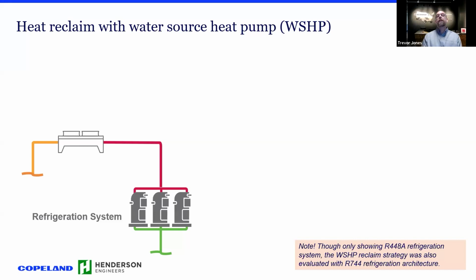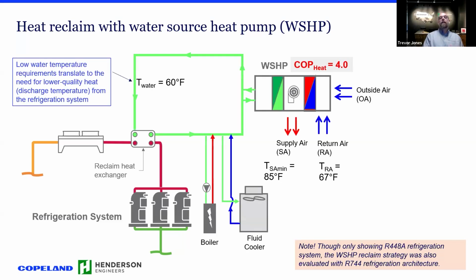So when we start getting into heat reclaim with the water source heat pump system, there's a heat exchanger on the compressor outlet, and our loop feeds through that heat exchanger. That allows us to basically shut off the boiler during certain periods of time if we have enough heat to meet the building's load.